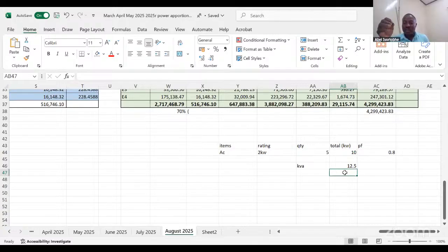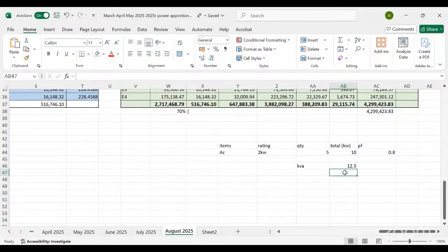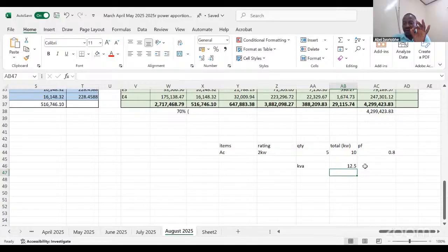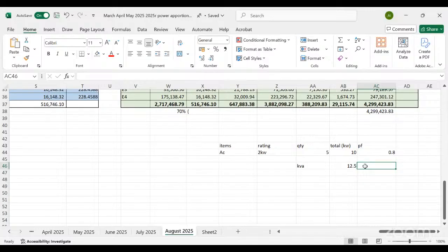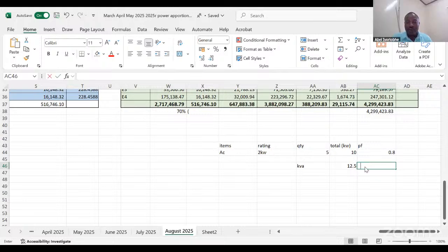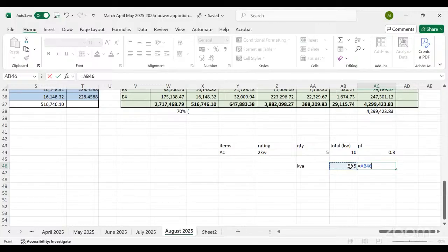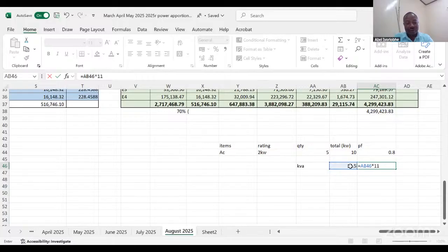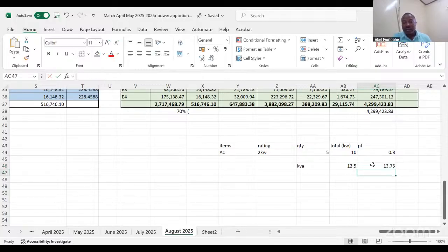Can you leave your generator size at 12.5 as you recommend to your customer? No. Like I told you, we don't recommend the exact value as your customer's rating. You add 5 or 10%. You understand? This one will now be equal to this times, let's say, 110%. So what you give them is about 13.75, let's say 14 kVA or 15 kVA as the case may be.